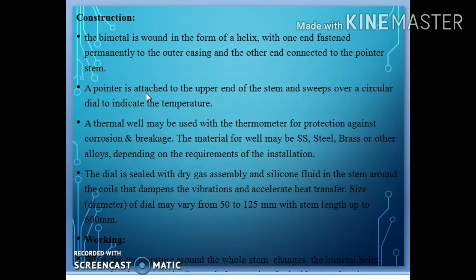The calibration of a bimetallic thermometer is generally done by inserting it in a fixed temperature bath, and its response is compared with that of a standard thermometer immersed in the same bath. The calibrations are marked for different bath temperatures, and then the temperature scale on the dial can be prepared. The performance characteristics are as follows. The static characteristic, the first one, is the accuracy. The accuracy of this thermometer is plus or minus 1% of the span if installed properly.